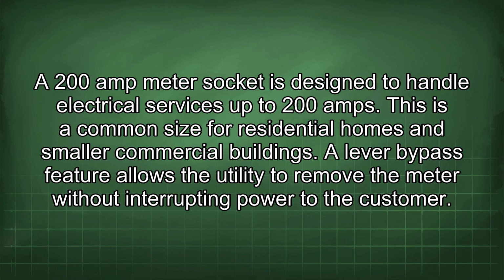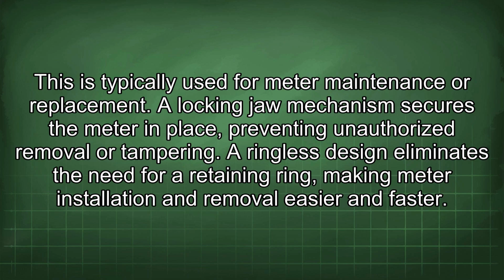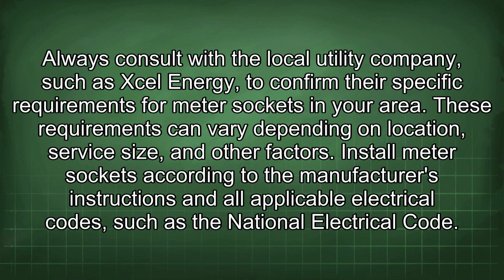A lever bypass feature allows the utility to remove the meter without interrupting power to the customer. This is typically used for meter maintenance or replacement. A locking jaw mechanism secures the meter in place, preventing unauthorized removal or tampering. A ringless design eliminates the need for a retaining ring, making meter installation and removal easier and faster. Always consult with the local utility company, such as Xcel Energy, to confirm their specific requirements for meter sockets in your area. These requirements can vary depending on location, service size, and other factors.